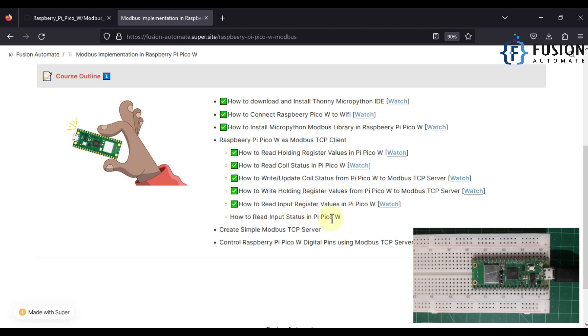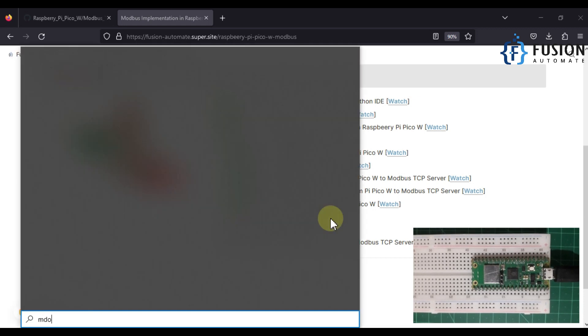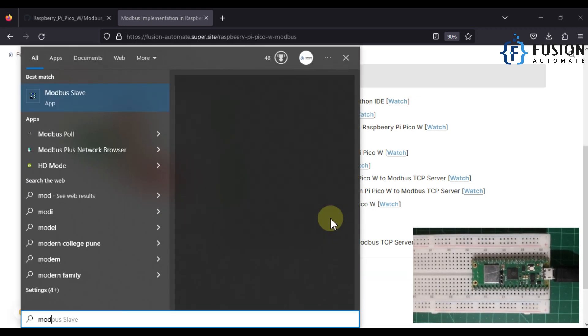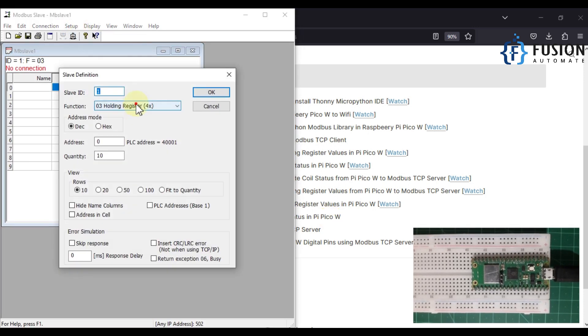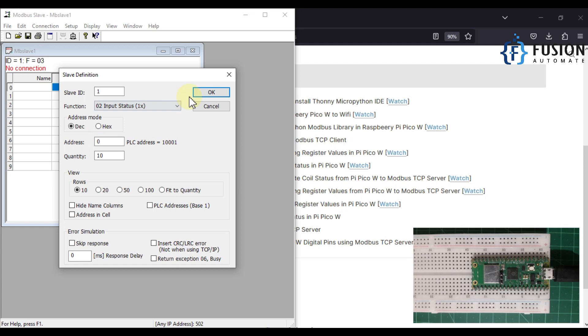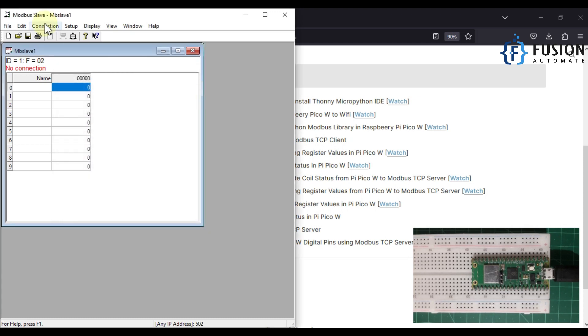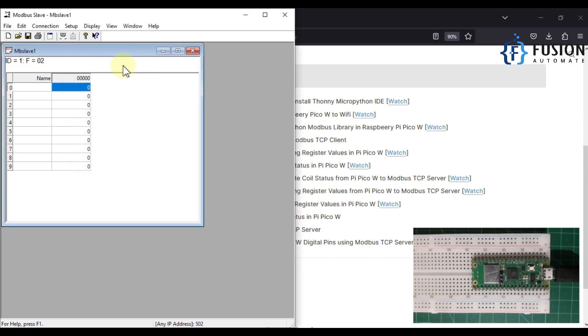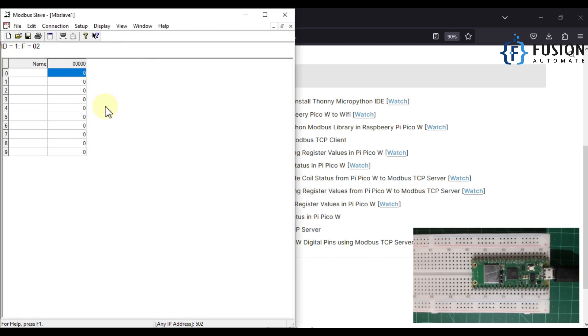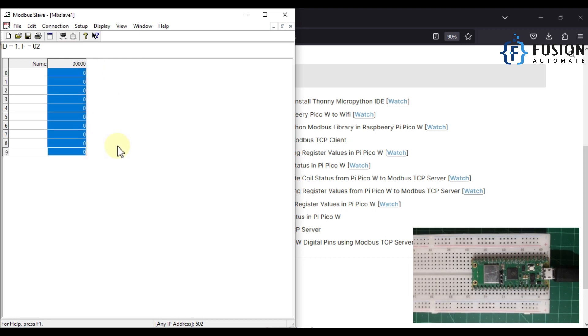First we have to set up our remote Modbus TCP device. As always, we are going to use Modbus Slave for this. We go to Setup, then Slave Definition, and we want to create a server with input status, so we select input status and press OK. Then we go to Connection, Connect, and press OK because the connection type is Modbus TCP/IP and the port number is 502. Our remote Modbus TCP server with 10 input statuses is now up and running.